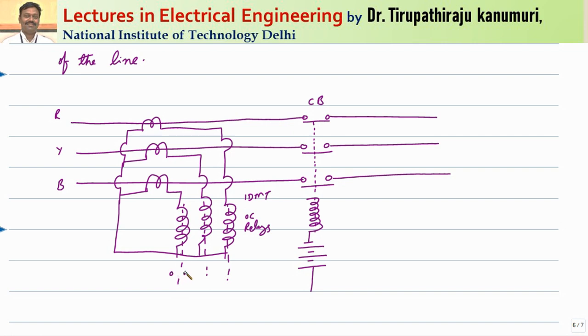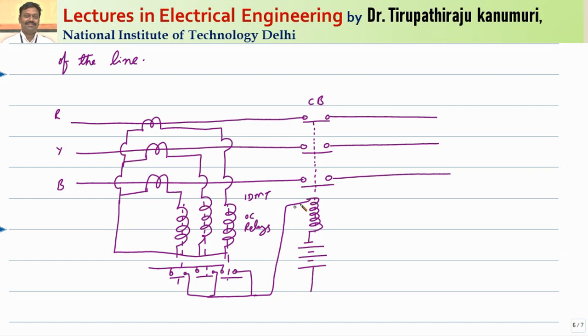Switches are connected in parallel to the relay outputs. Whenever any one of these switches is closed — whether the first, second, or third switch — this will activate the activating circuit for your circuit breaker and the relay will trip. This is the trip coil of the circuit breaker, and the circuit breaker will trip.